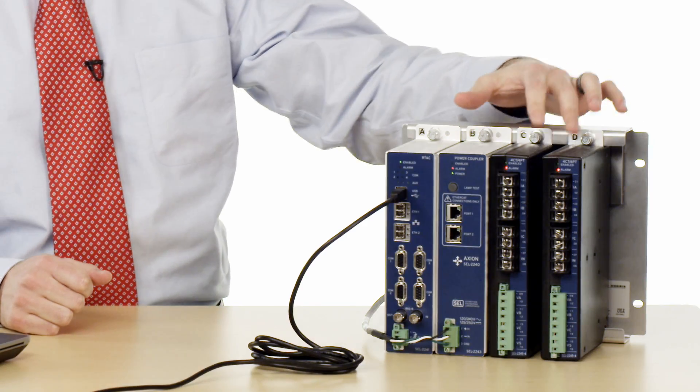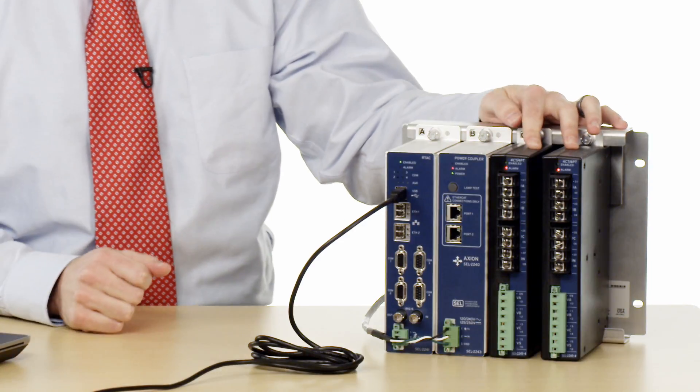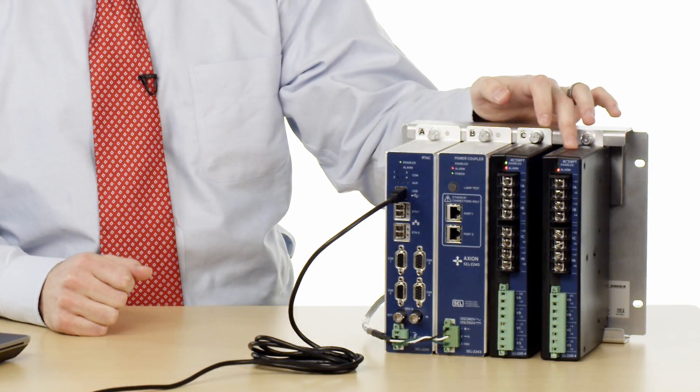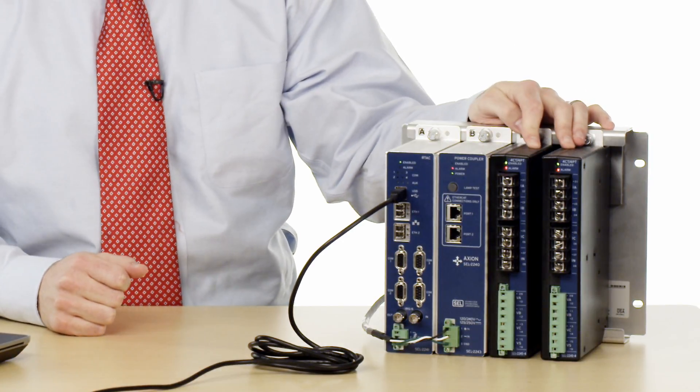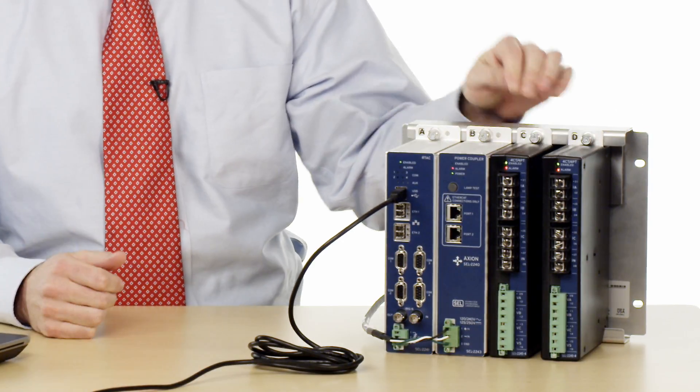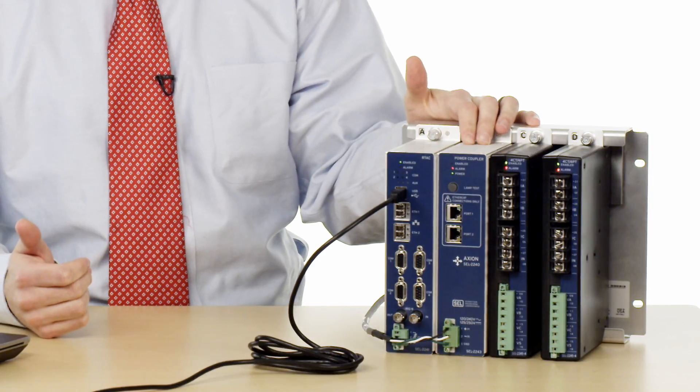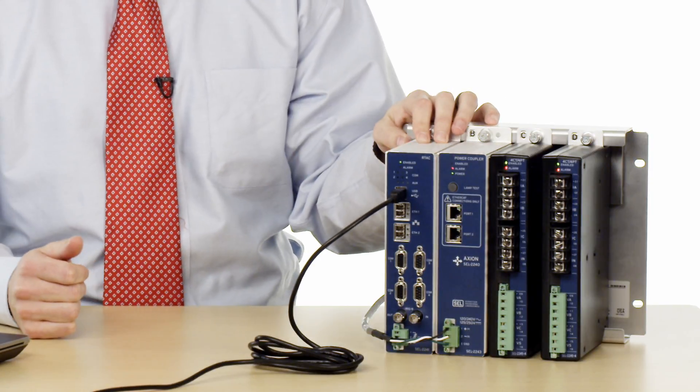The equipment I have here includes two AC analog input modules that can measure both current and voltage phasors, a 2243 power coupler, and a 2241 R-TAC.